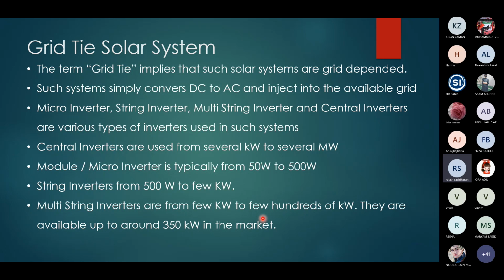Micro inverters are in the range of a few watts, maybe up to 500 watts. String inverters range from 500 watts to a few kilowatts, but they're getting obsolete. Multi-string inverters go from a few kilowatts to a few hundred kilowatts—I believe Sungrow, the manufacturer, has even released a 350 kilowatt string inverter. Central inverters have their own transformer, monitoring and power transmission devices, and come in multi-megawatt scale—8, 9, 10, 20, etc. These are used for large-scale megawatt power plants, not something we'd need for our homes.